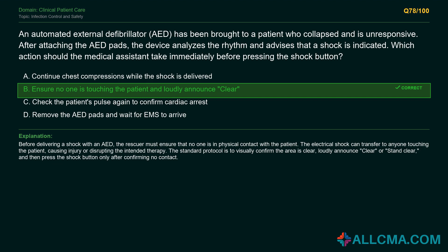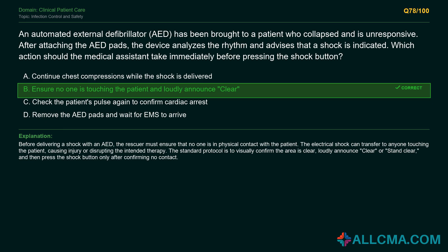The correct answer is B. Before delivering a shock with an AED, the rescuer must ensure that no one is in physical contact with the patient. The electrical shock can transfer to anyone touching the patient, causing injury or disrupting the intended therapy. The standard protocol is to visually confirm the area is clear, loudly announce clear or stand clear, and then press the shock button only after confirming no contact.